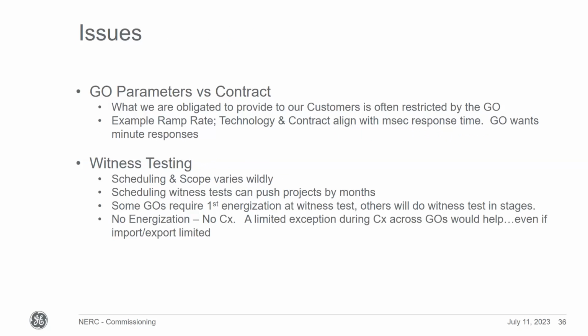Our contracts obligated us to provide certain things to our customers, but we've come to find those parameters are often restricted by the grid operator. A good example is ramp rate. The technology we deal with in IBRs and the contracts we sign are aligned with millisecond response times, but often when we get to commissioning, we're told to slow down. The grid operator wants minute-level response times versus millisecond.